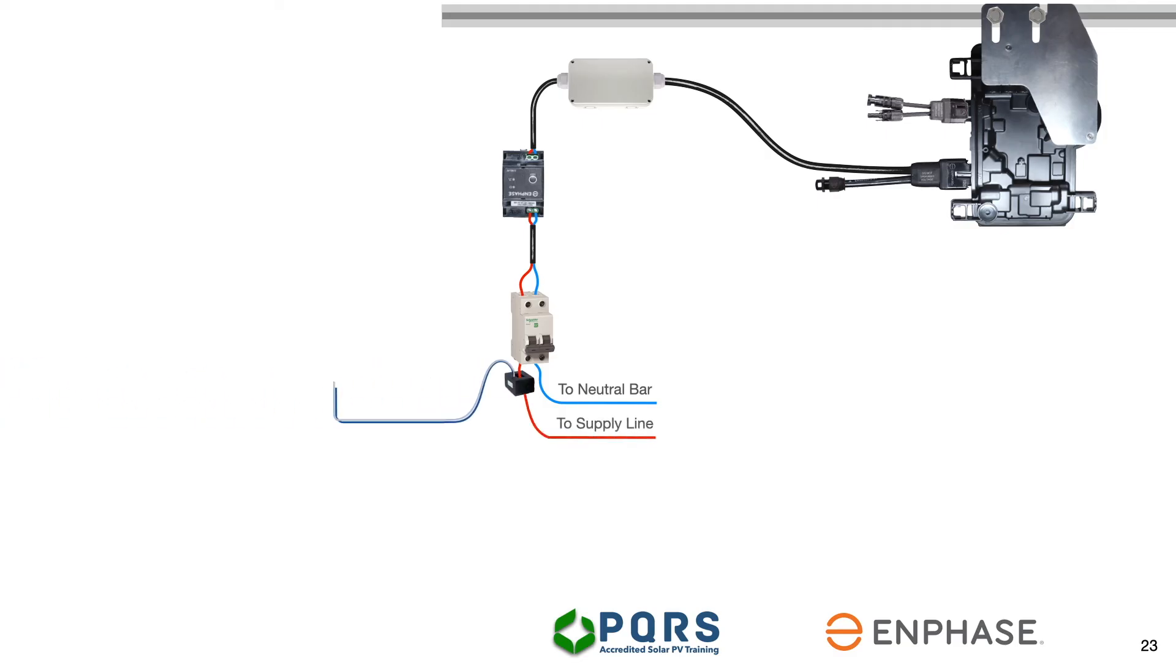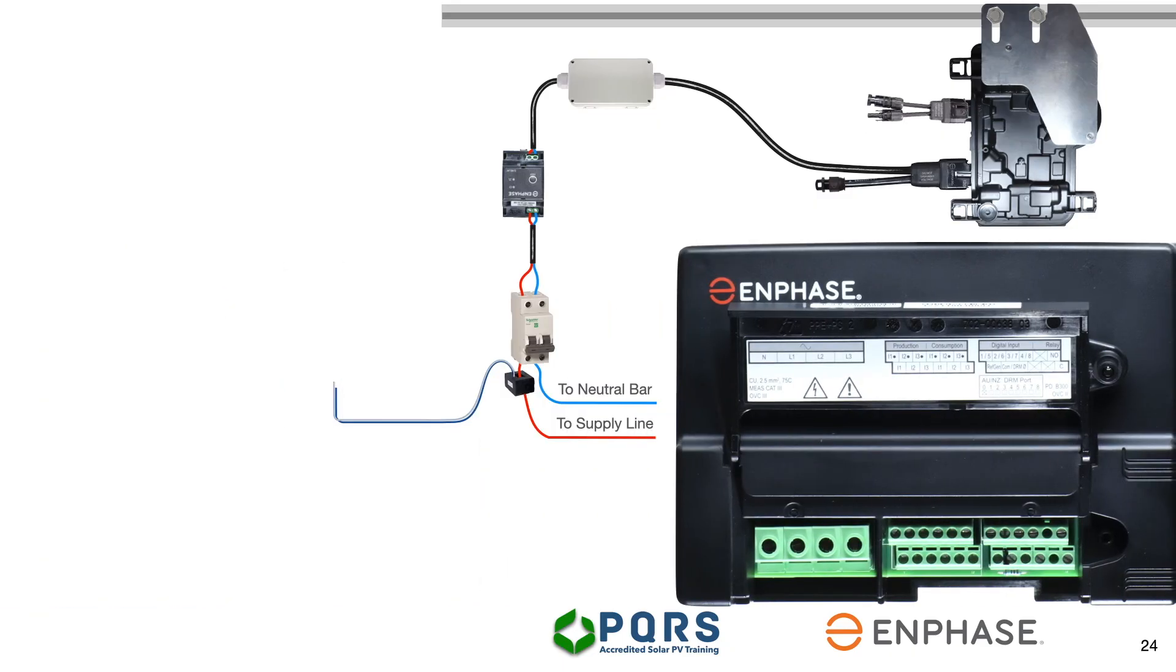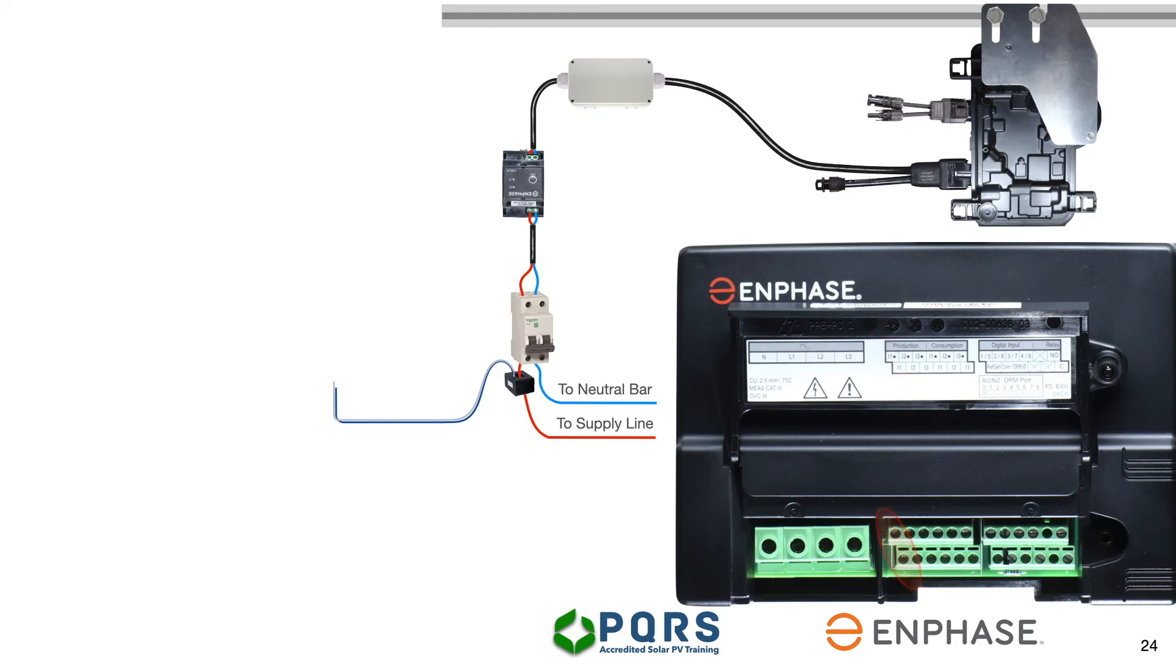A current transformer or CT will be connected to the line coming from the microinverter. This CT will provide the production-related data to the Enphase Envoy. The Enphase Envoy is the device that sends production and consumption information to the online portal. Pay particular attention to the termination points for production and consumption.